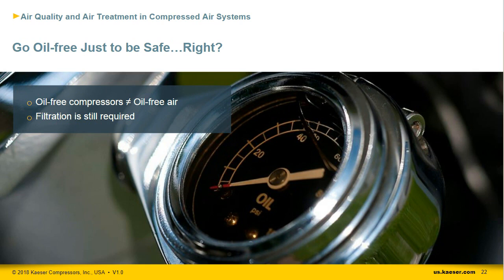Our last misconception has to do with the type of compressor selected. Typically, oil is bad. I need an oil-free compressor. But just because you have an oil-free compressor, like Michael mentioned before, that doesn't automatically guarantee you have oil-free air. You still need to have adequate filtration.